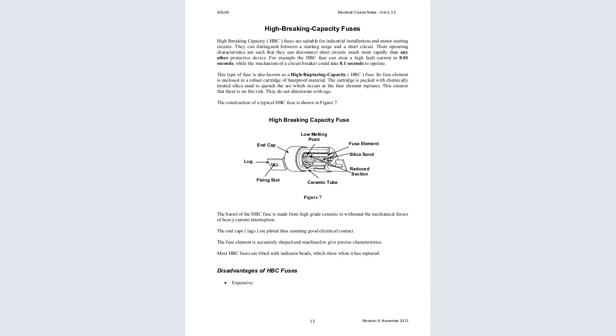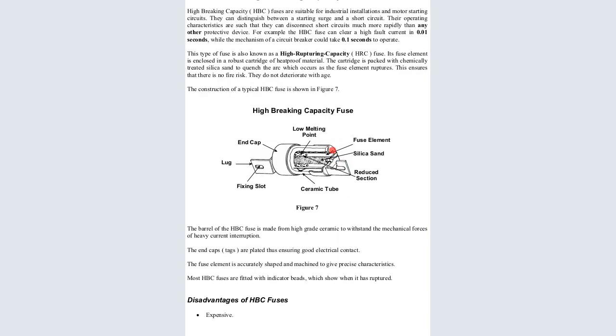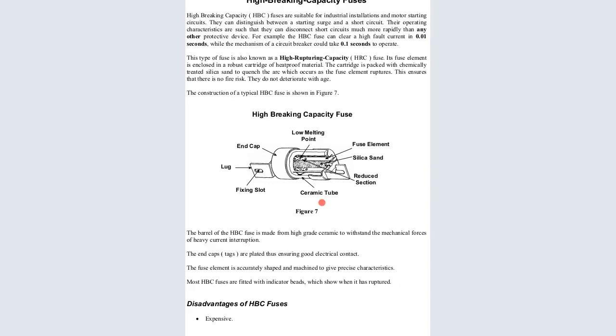So the construction of a typical HBC fuse is shown here. Now look at it and the parts. We have the lead, the lug. This lug is where we are going to fix the nuts. The fixing slot is here. The end cap is there. The low melting point fuse elements are here, which can melt in case of short circuit. And then we have the reduced section, the ceramic tube and the silica sand.